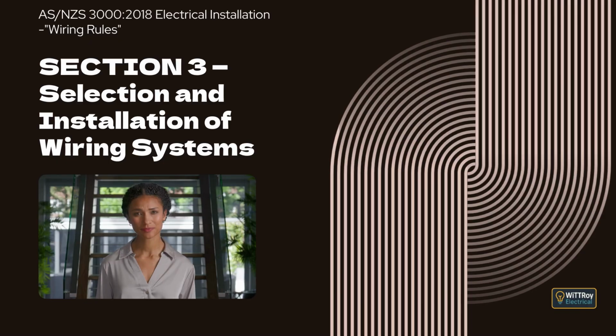Clause 3.9.9, Selection and installation to minimize the spread of fire. This clause introduces fire safety considerations for wiring systems. Clause 3.9.9.1, General. This clause explains that wiring systems must be selected and installed to minimize the spread of fire and must not reduce the fire performance of the building.